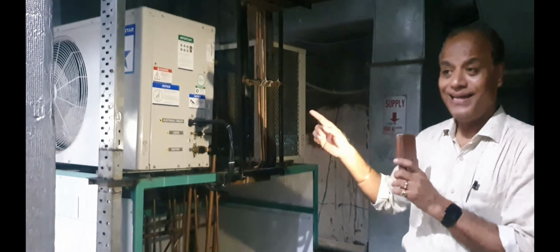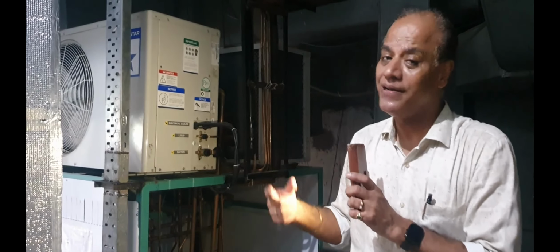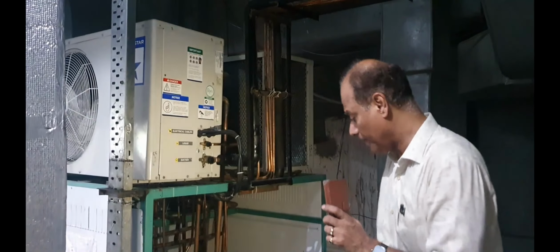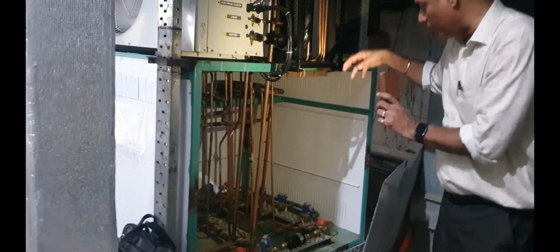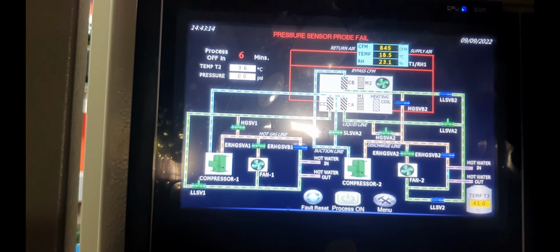These 2 condensing units, each of them, give us about 25 kW of heating. This is all the basic infrastructure: the refrigerant piping, the solenoid valves, the heat exchangers which generate this hot water. When you look at this PLC, the hot water is at about 41.1 degrees centigrade. In AHU number 4, the temperature is about 18.5 degrees centigrade and the RH is about 23.2%, 23.2% at 18 degrees centigrade. That's the performance of this machine.